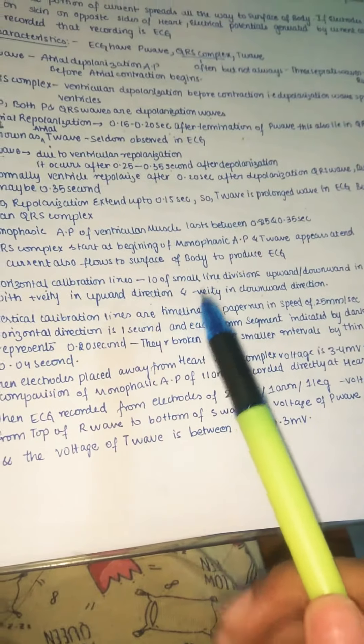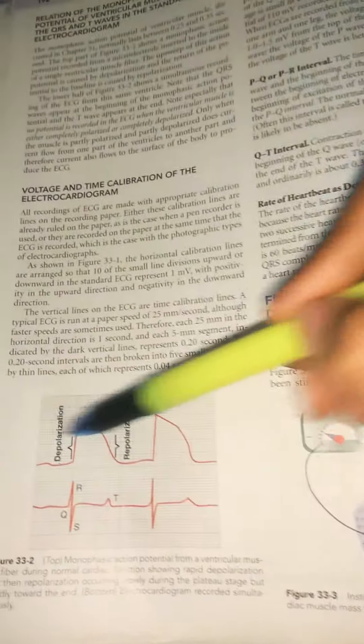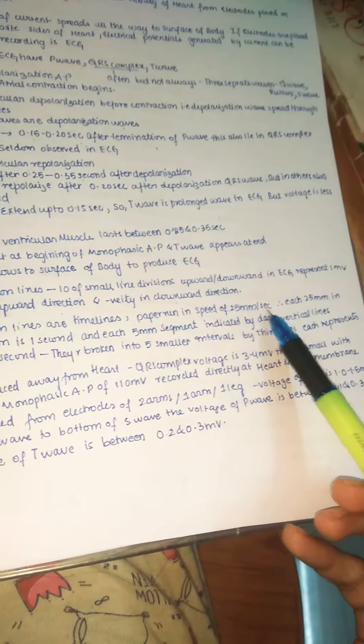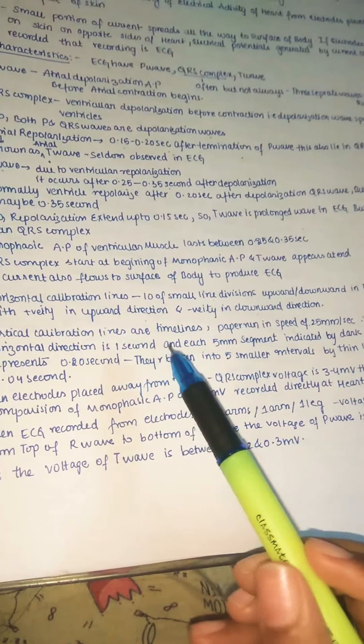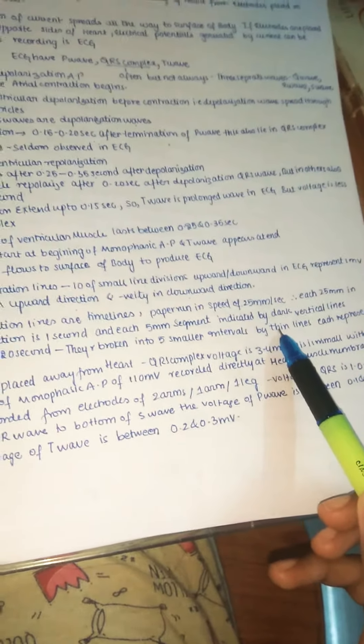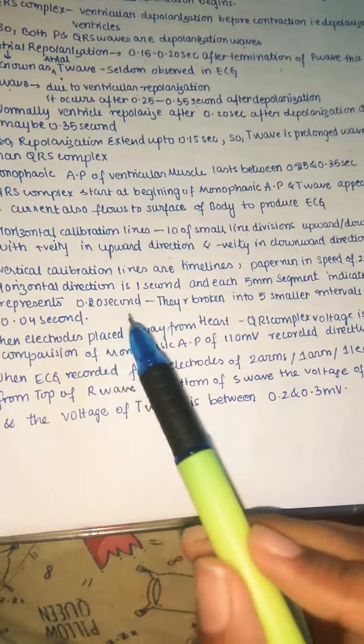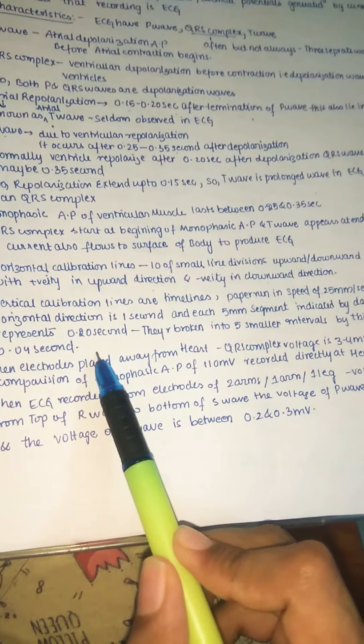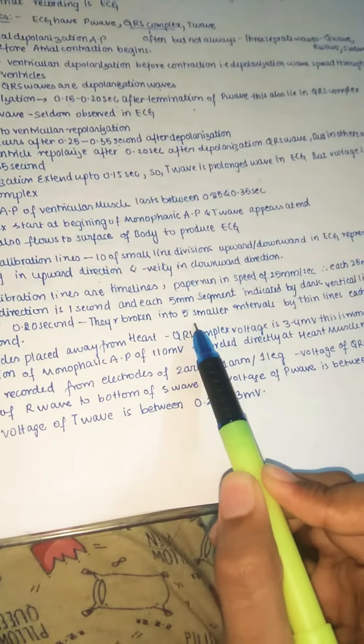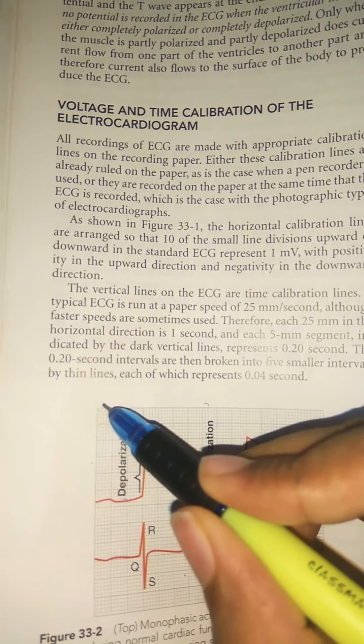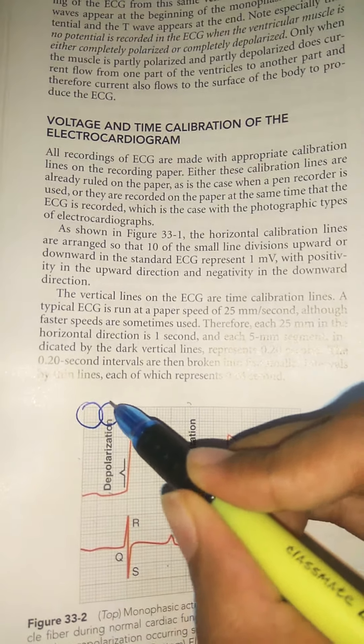The ECG paper runs at a speed of 25 millimeters per second. Each 25 millimeters in the horizontal direction equals one second. Each 5-millimeter segment, indicated by dark vertical lines, represents 0.20 seconds. These are further broken into five smaller intervals by thin lines, each representing 0.04 seconds. Remembering these time values makes it easier to calculate ECG-related measurements.